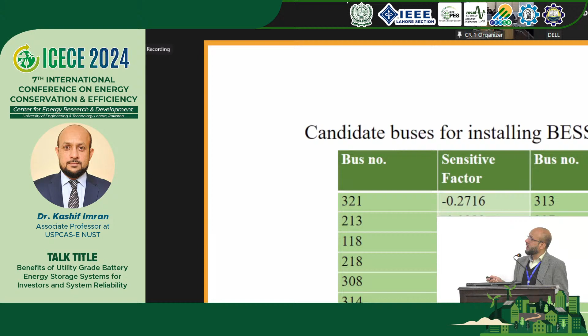So when we determined the optimal location on the basis of the Z bus sensitivity factor, we determined that these buses are the optimal locations, with bus number 321 being the most optimal and this one being the least optimal in this list. So if we are going to install three batteries, we can choose these three locations, and that will be the best location. And if we have more investment, we can choose five or so on.